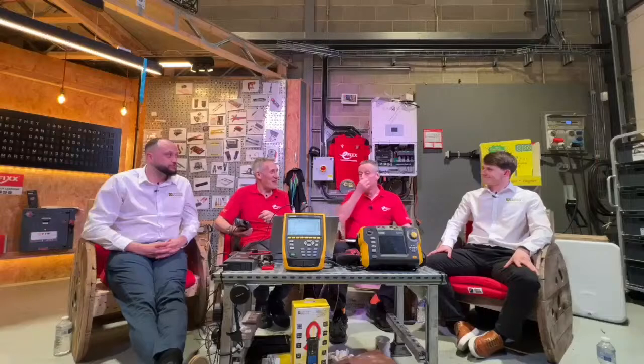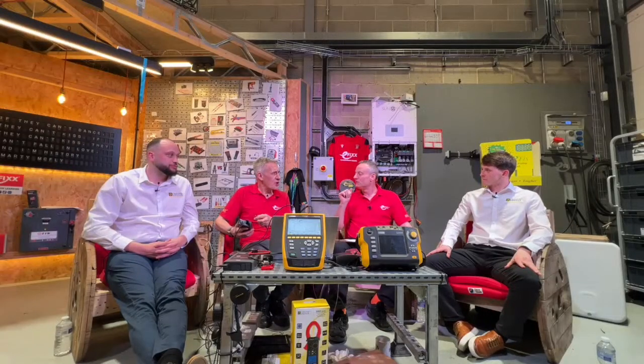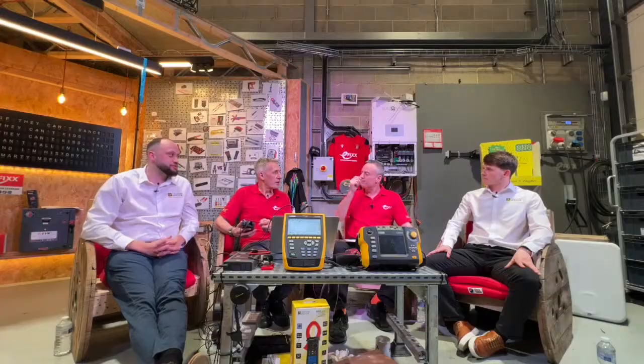People use the crude way of doing PEN fault protection - anyone who makes PEN fault protection, apologies, get them there, just from Gordon. Yeah, they typically work on over voltage, and it's not that high actually. So we know we've got plus 10, minus 6. Exactly - the ESQCR stipulates that you're allowed 230 volts plus 10 or minus 6 percent.